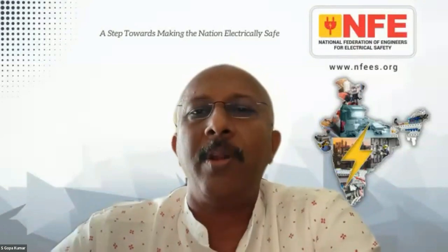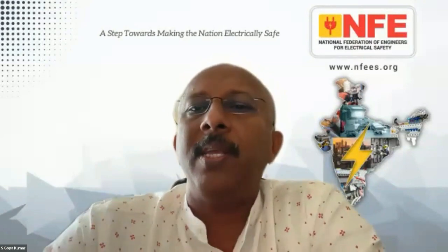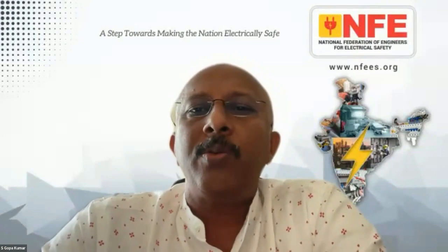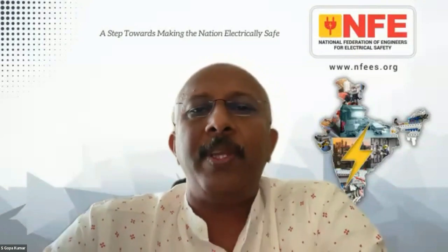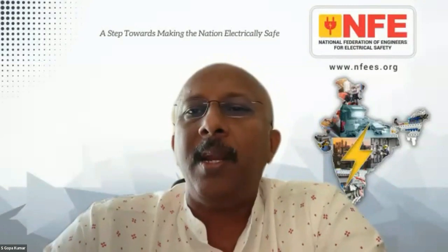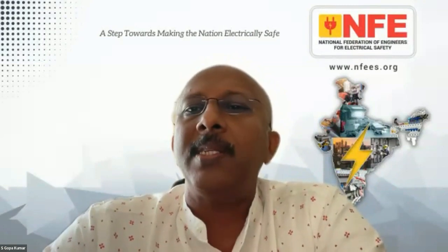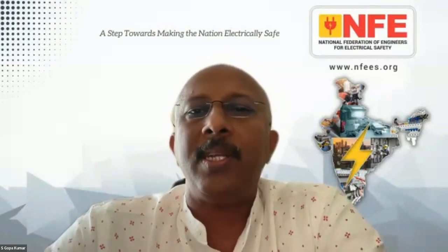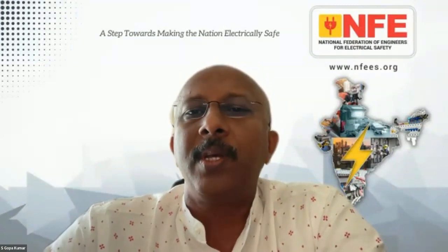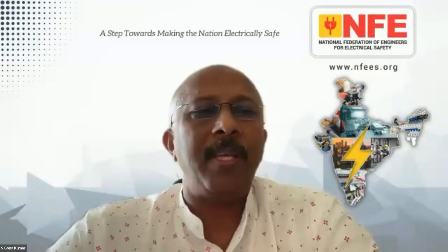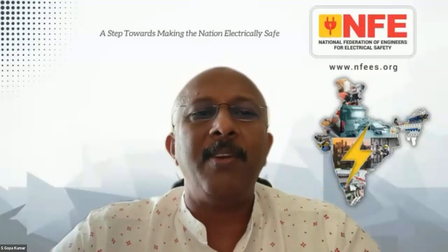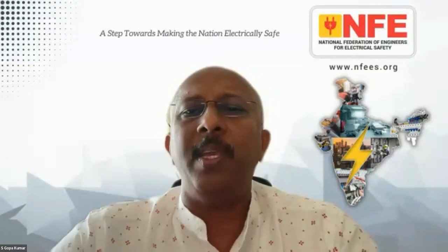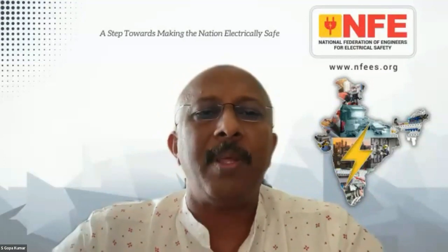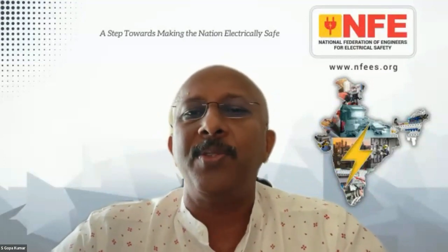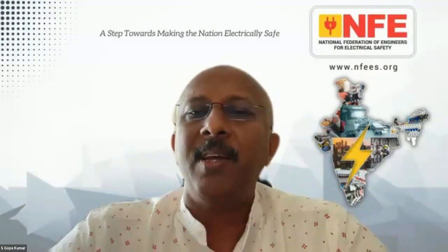You have to size it according to the expected fault current, whereas for an earthing conductor, you don't need to size like a PE conductor. Some fixed sizes can be used. For the earthing conductor, the important things to consider are corrosion and mechanical strength. For the PE conductor, it is fault current. Actually, this subject is confusing. Sometimes it's called PE conductor, sometimes earthing conductor, sometimes equipotential bonding conductor, and it is a little bit confusing.